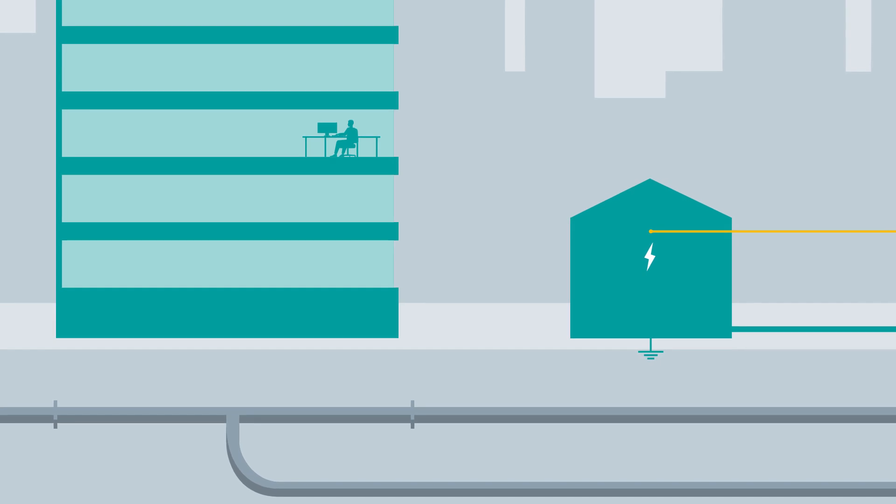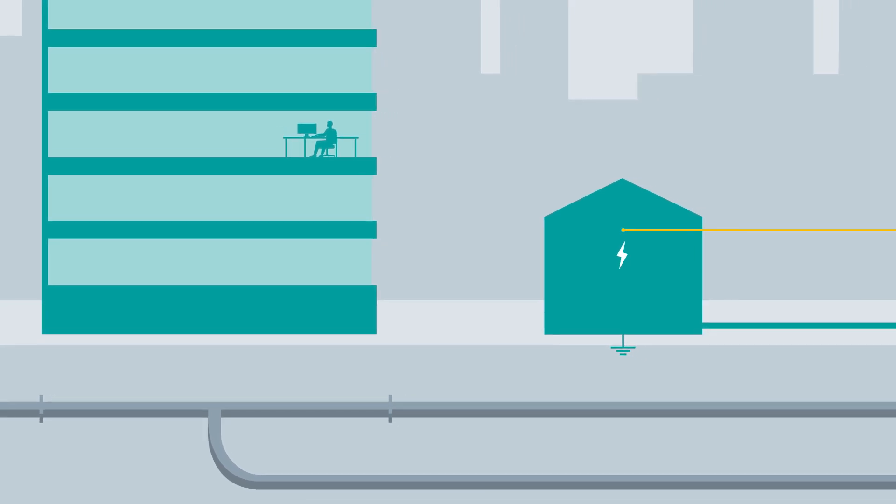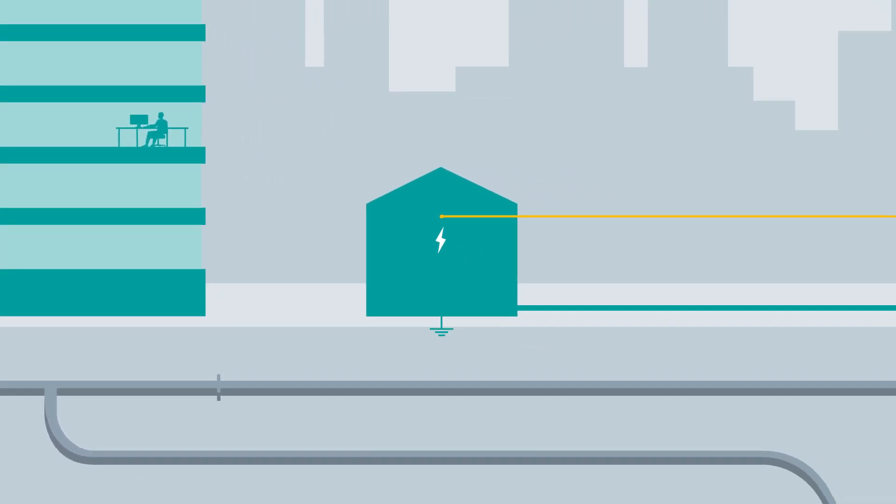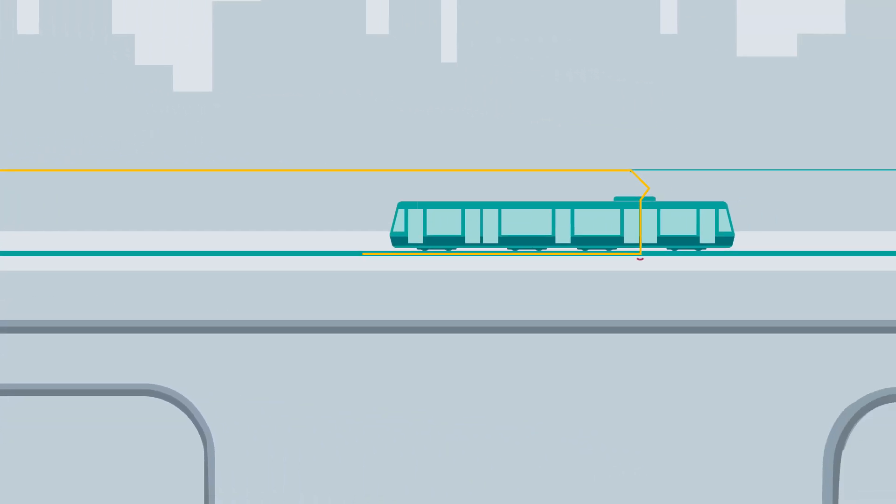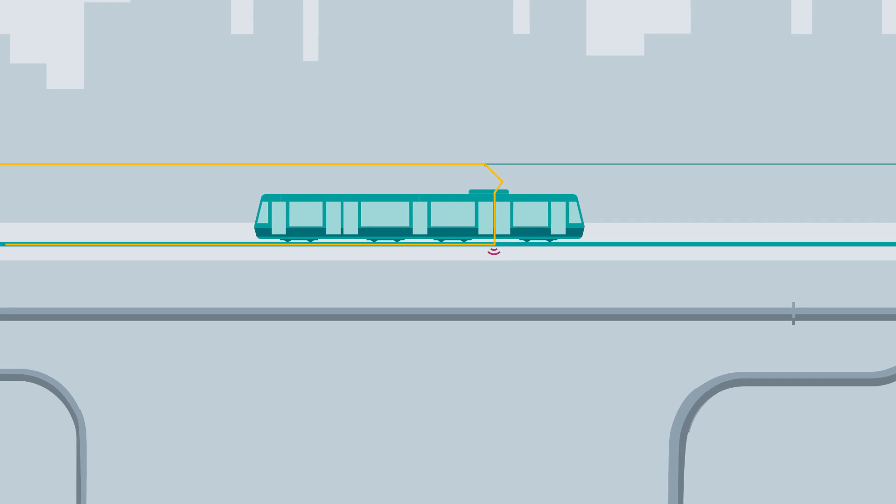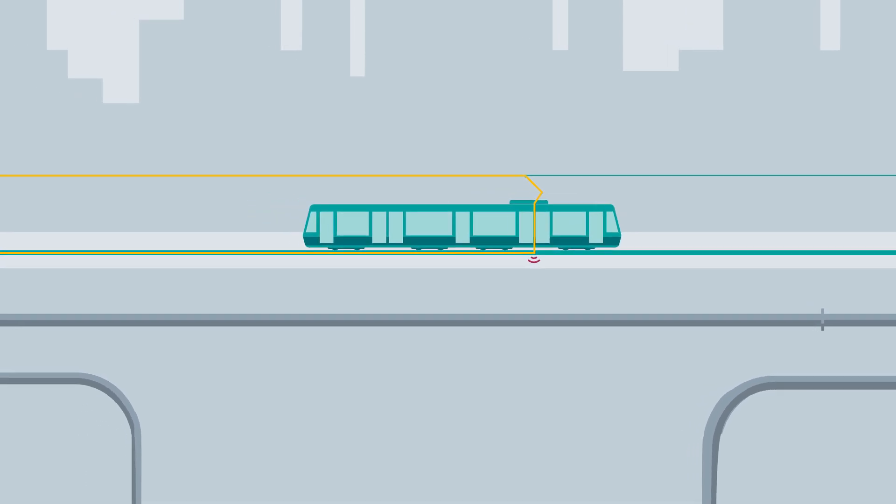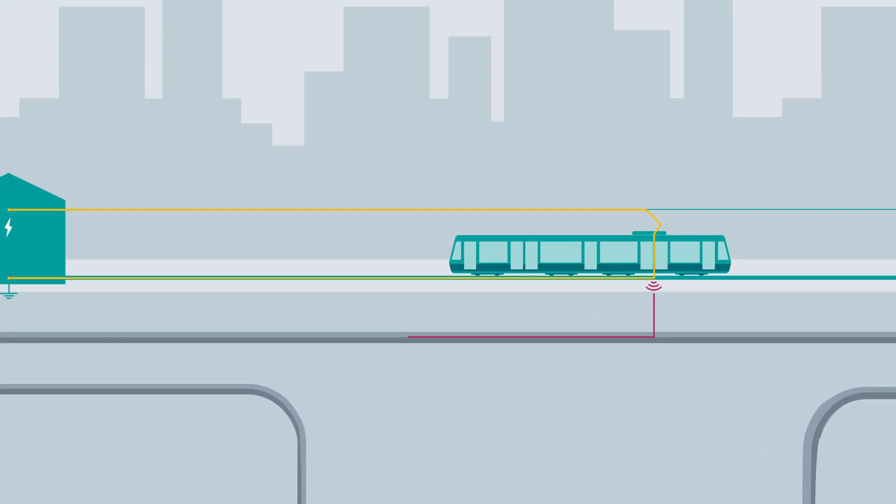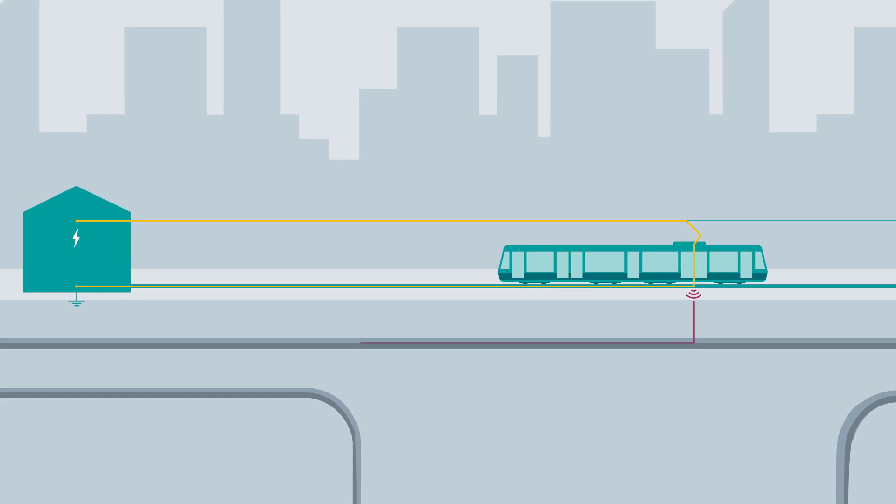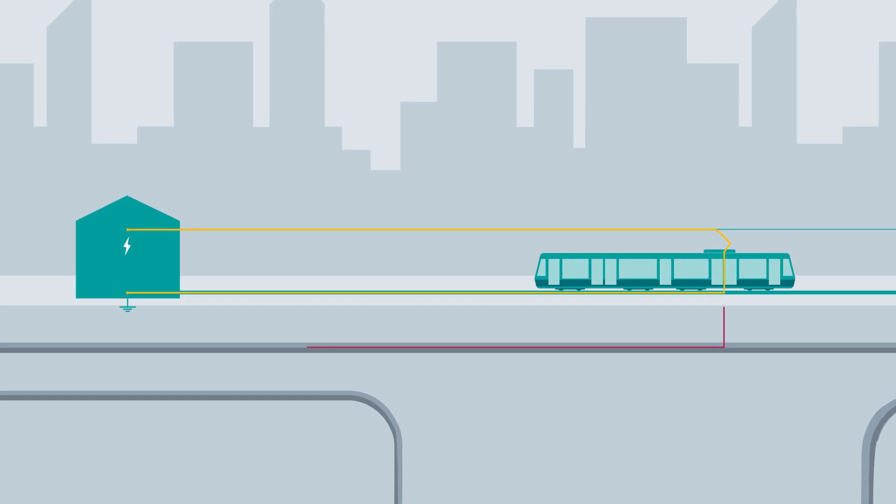Unfortunately, isolation between the rail potential and the earth potential in reality is never ideal. A part of the traction current therefore flows back to the substation as a stray current via the earth.